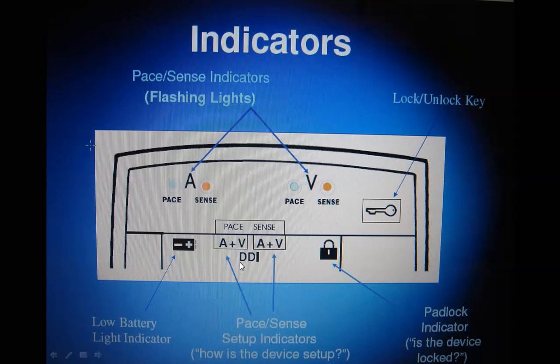So to re-emphasize, the 1st alphabet means the chamber paced, the 2nd alphabet the chamber sensed, the 3rd alphabet is response to sensing, and the 4th alphabet is the rate modulation, meaning that if the patient is running, the heart rate should be increasing as modulated by the pacemaker. Also, the 5th alphabet we said is the shocking therapy for ICD, either anti-tachycardia pacing or DC shocking. However, because it is a temporary pacemaker, the 4th alphabet cannot be there, neither the 5th alphabet. Why? Because it is an external device. So there's no way you can get a 4th alphabet.